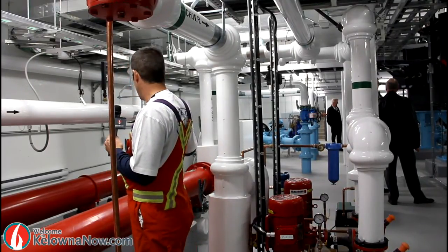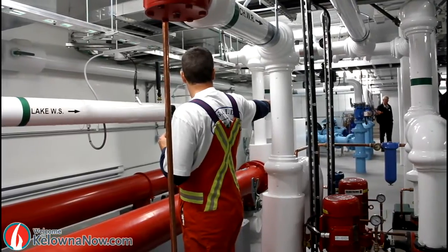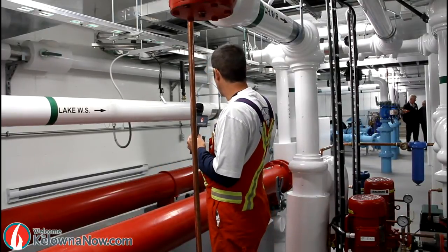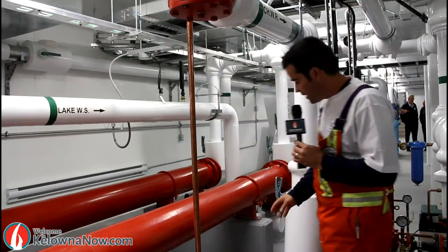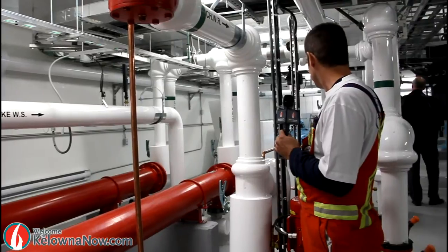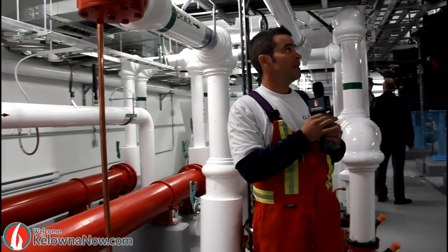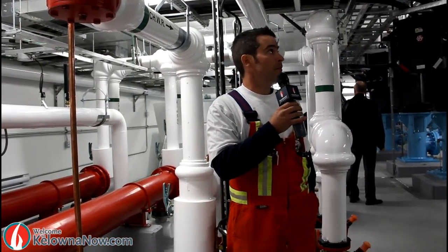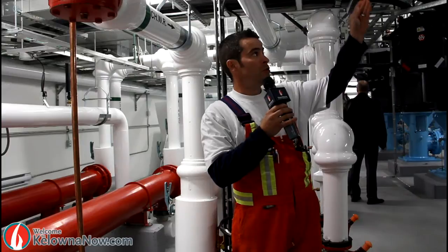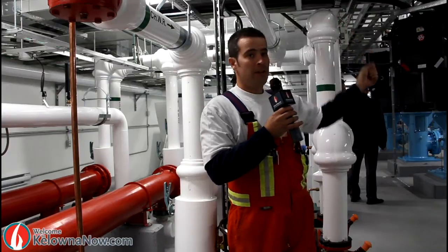The cool water from the lake will pass through this heat exchanger and will in turn be dumped back out into the wet well. The idea of running that lake water through is to cool the glycol, which is in the closed loop system, which then passes through these three horsepower motors. These are all pumped up into an air handling unit just above us. That air handling unit has a radiator inside of it with a blower motor, which then pushes the cool air coming off the radiator through a ventilation unit onto the electric motors to cool them down.